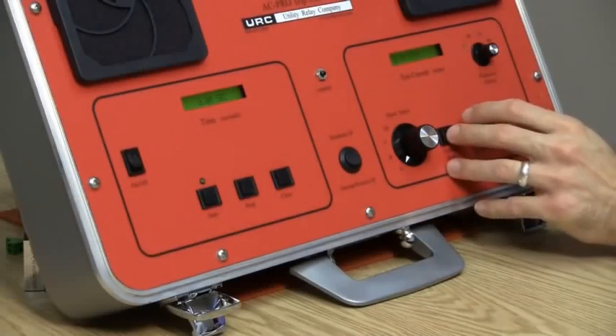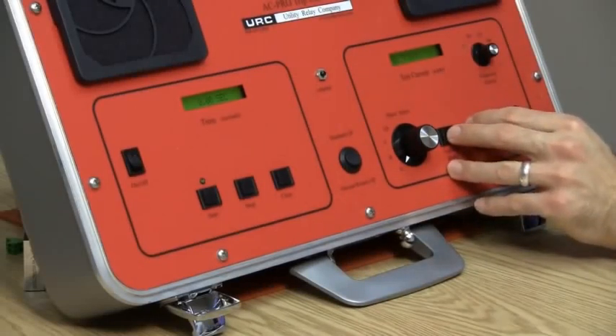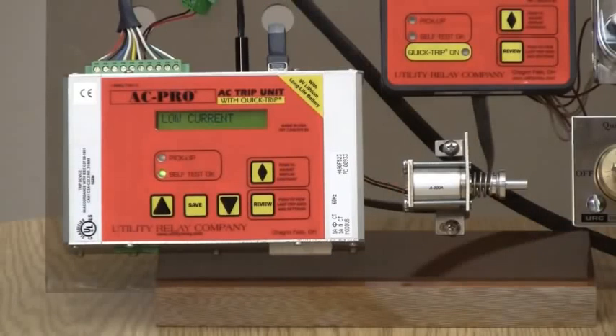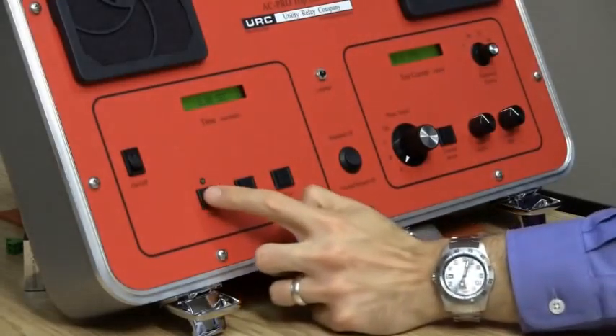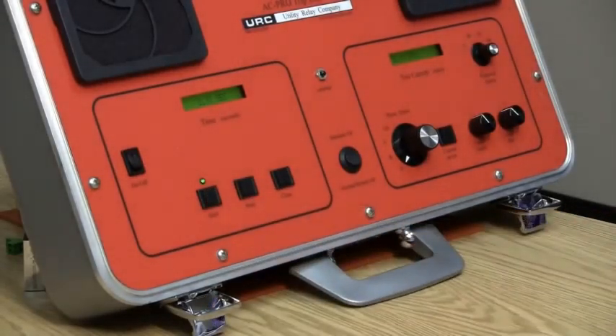I'll adjust the test set for a 3 times overload on phase A. Based on the settings in the AC Pro, it will fire the actuator in about 8 seconds. Pushing the start button on the test set will start the test set.